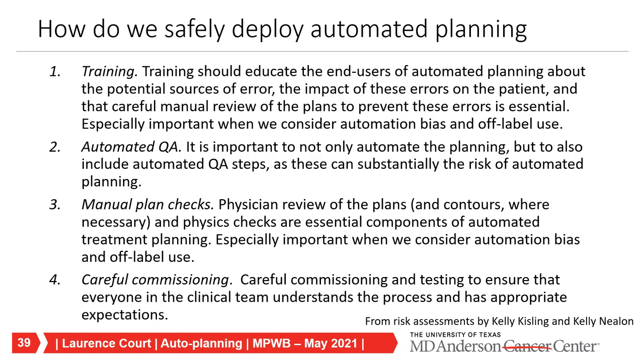What does all this tell us about safely deploying automated tools? There are four main things to consider. First, training: we must educate end users about the tools, what can go wrong, the impact of failures, and risks like automation bias and off-label use. Second, automated QA: automating some QA steps adds another level of safety without replacing manual steps. Third, manual plan checks: physician review of plans and contours, plus physics checks, are essential components of automated treatment planning—that patient with hip implants is an extreme example of why. Fourth, careful commissioning and testing of tools to ensure the clinical team understands the process and has appropriate expectations.